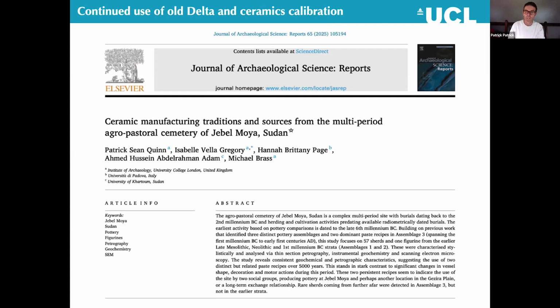And this is Jebel Moya in Sudan. I showed you a study before where we used that, and so we got the old machine because we want to use the same calibration. If I get back to the Terracotta Army to analyze those, I'll need to pull out that machine as well. So that's an issue, keeping these machines that have got bespoke calibrations around, keeping them working. If the detector needs to be replaced, then the calibration, I believe, is not valid anymore. So there's an issue with longevity with that.